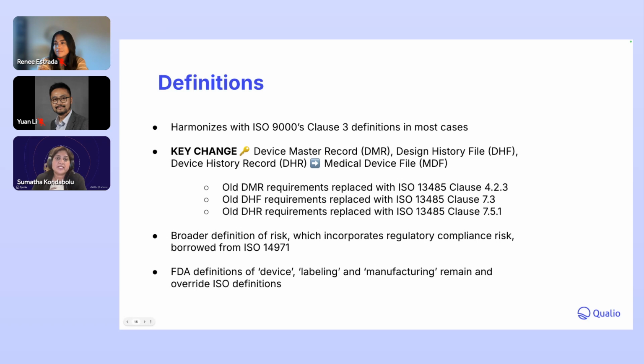And a key important point to highlight here is to integrate regulatory compliance risk alongside your safety and performance risk processes, acknowledging ISO 14971's broader definition of risk. For example, are you doing everything you need to do to proactively safeguard your organizational state of compliance? In the same way, you would integrate your device itself. So this is where you will be questioning, identifying and performing the risk assessment across the quality management system regulations to comply with those regulations across your quality management system.